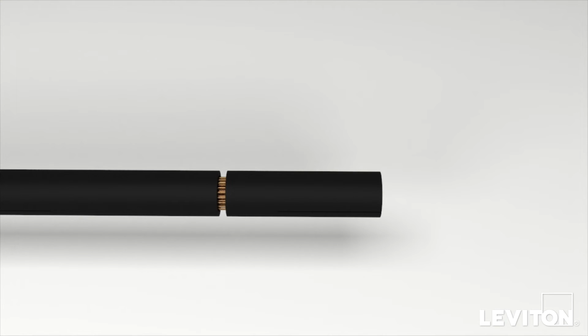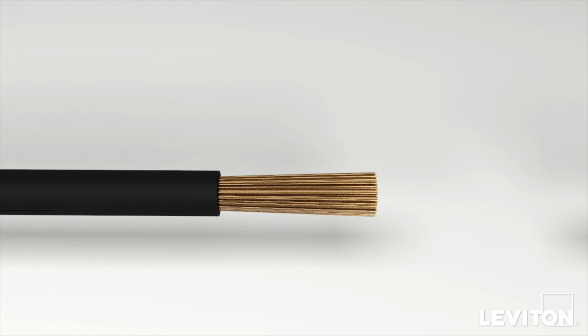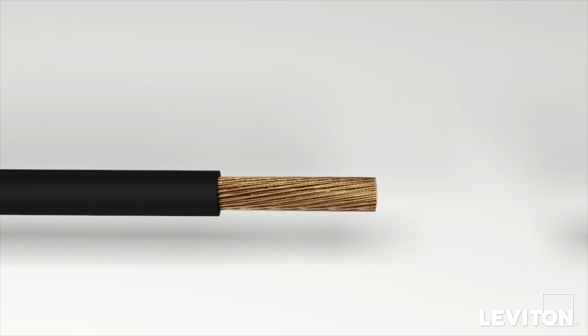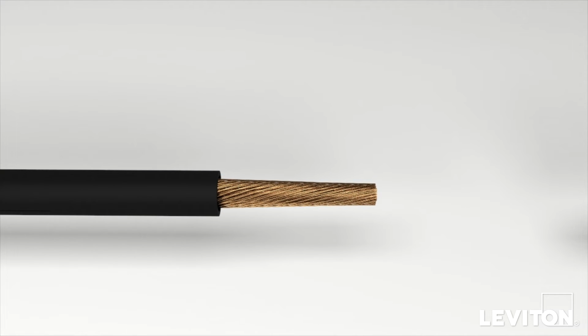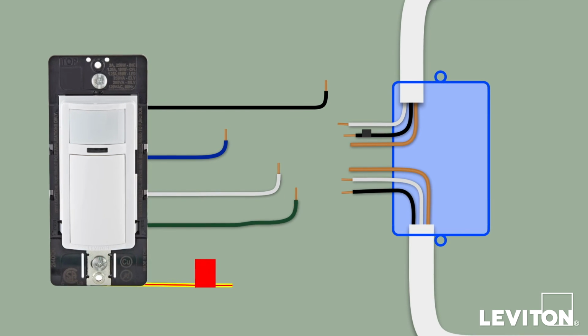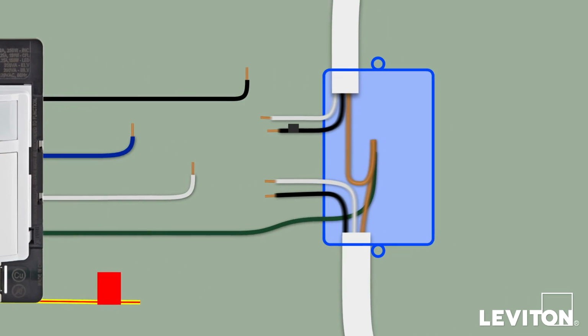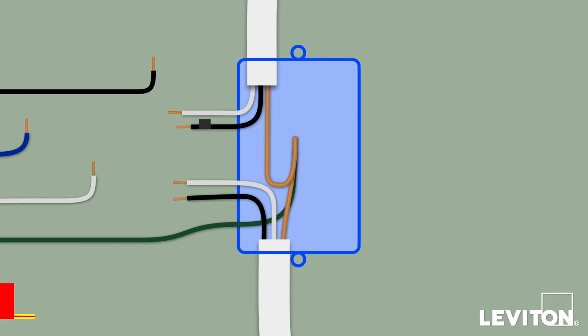With your fingers, pull firmly on the insulation to remove the pre-stripped section of the product's leads. Do this for each lead wire. Twist each of the lead's exposed stranded copper wires in a clockwise direction. Next, twist the green ground lead on the device to the ground wires in the wall box in a clockwise direction. Insert the twisted wires into a properly sized wire connector and continue twisting until the conductors bottom out and cannot be twisted further. Give the wires a tug to ensure they are firmly held in the wire connector and dress with electrical tape to ensure stability.